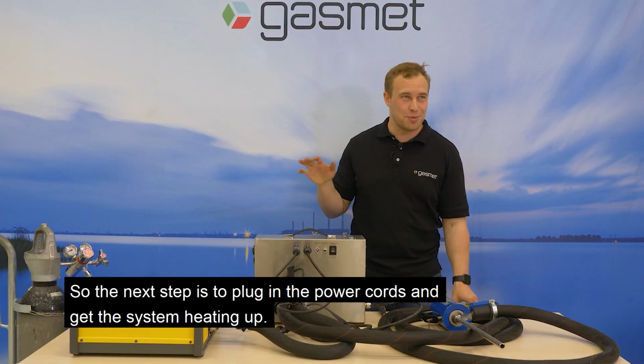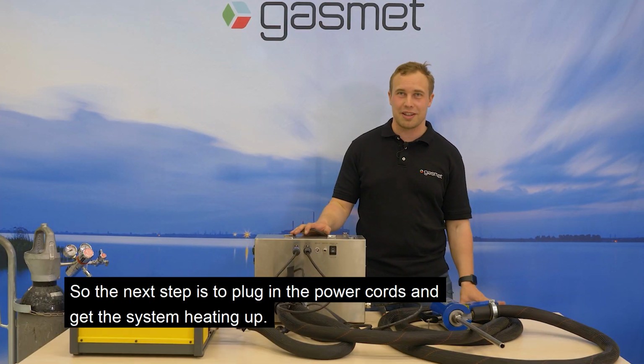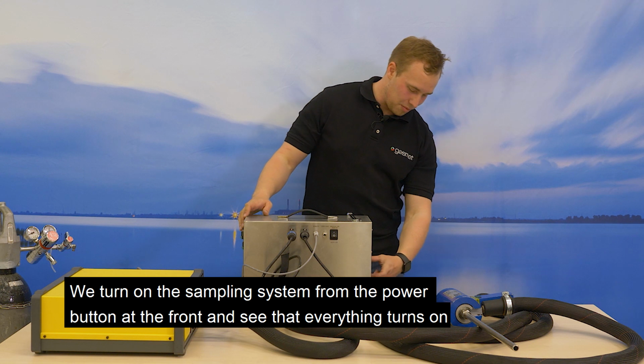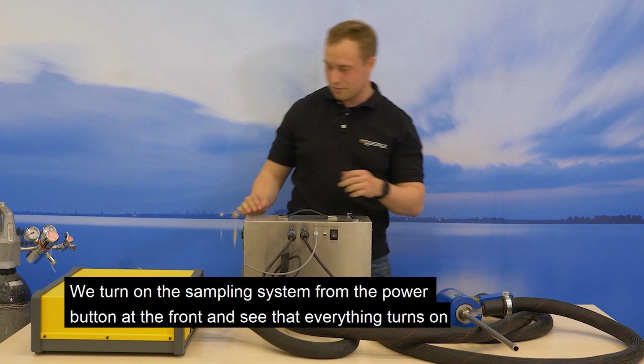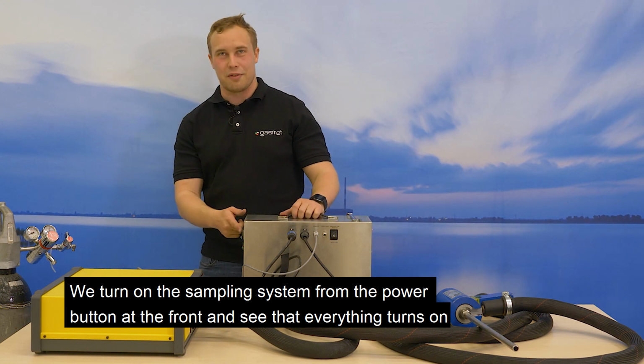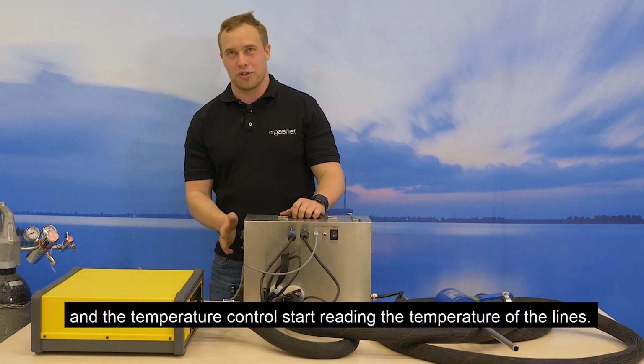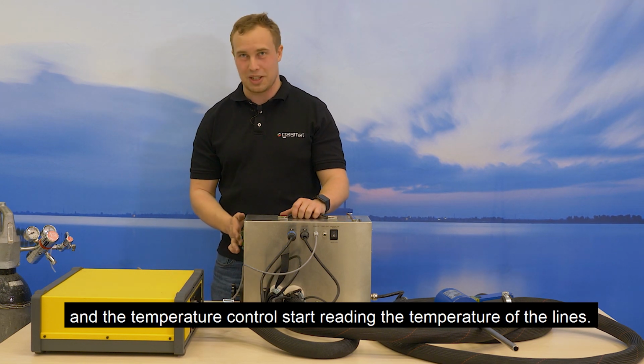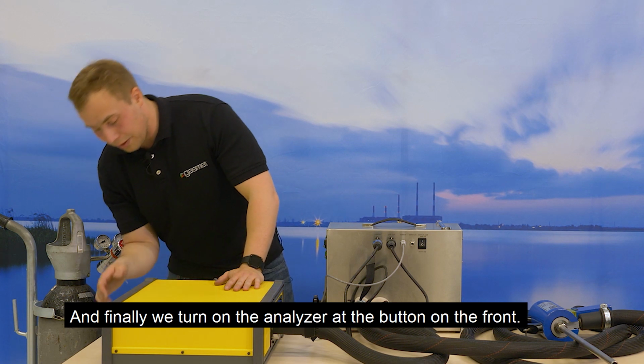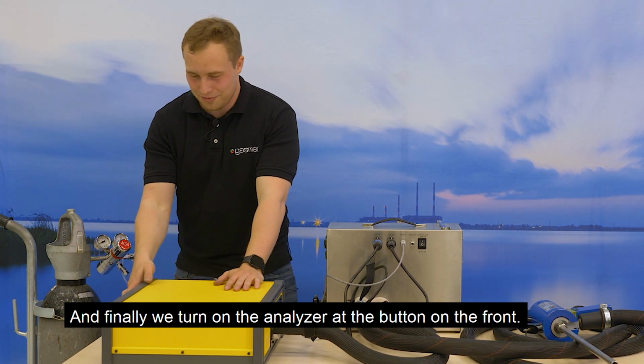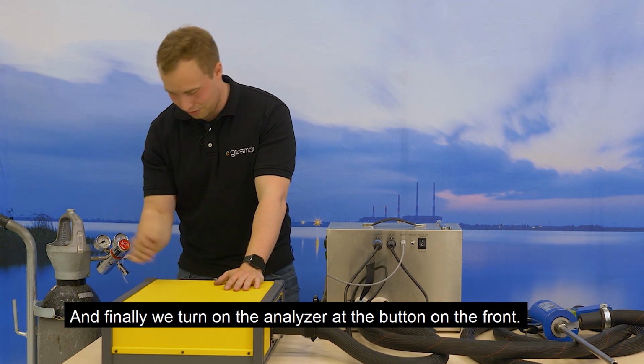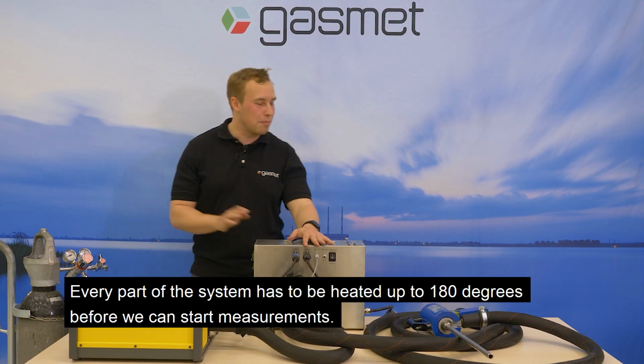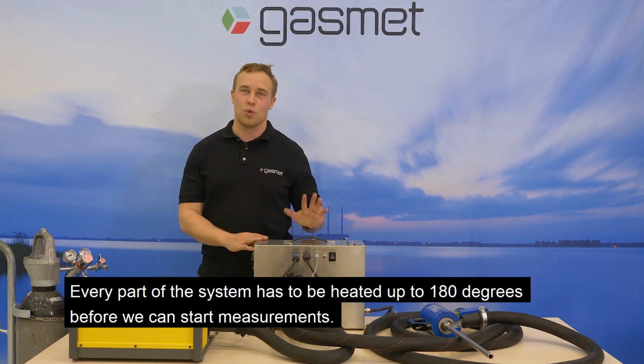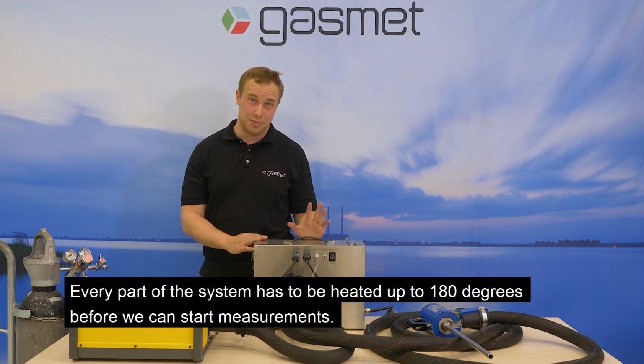So the next step is to plug in the power cords and get the system heating up. We turn on the sampling system from the power button at the front and see that everything turns on and the temperature controllers start reading the temperature of the lines. And finally, we turn on the analyzer at the button at the front. Every part of the system has to be heated up to 180 degrees before we can start measurements.